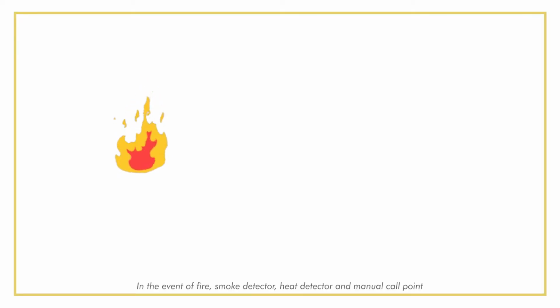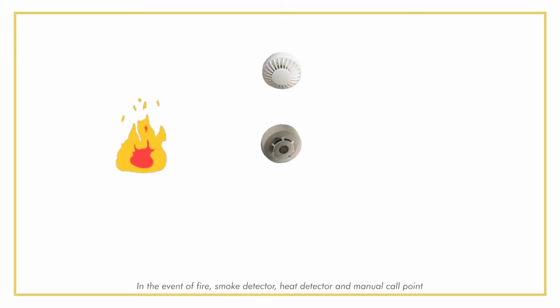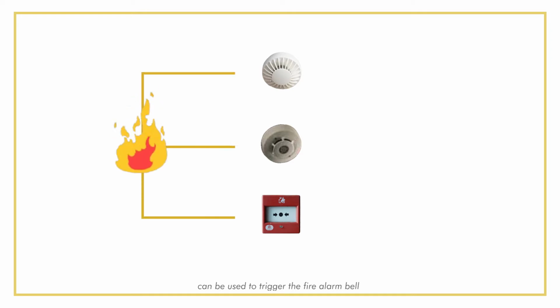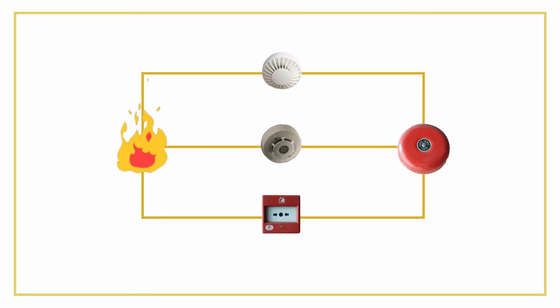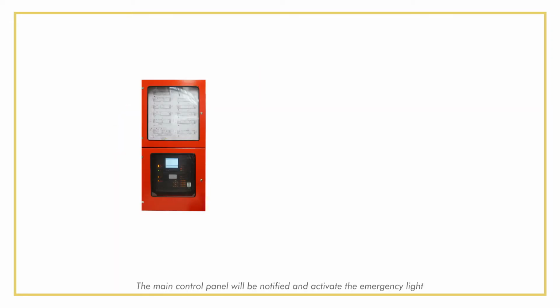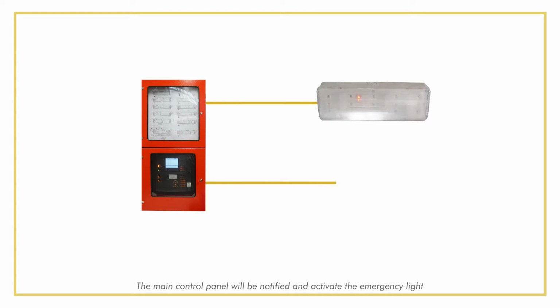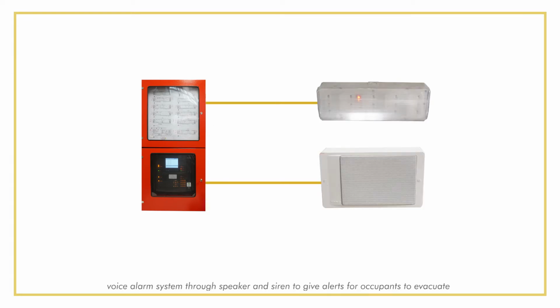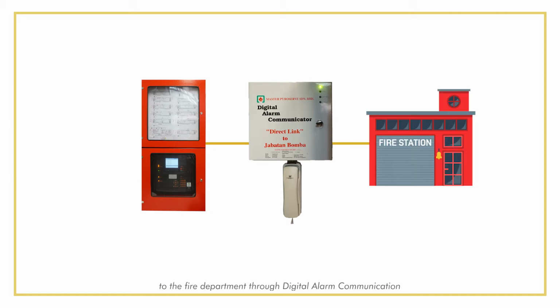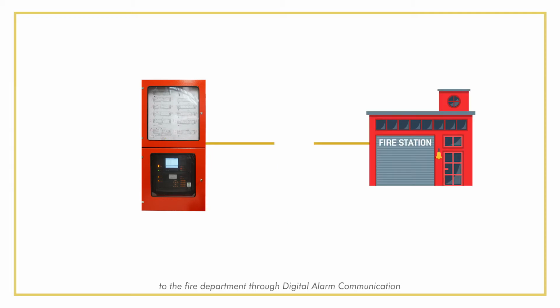In the event of fire, smoke detectors, heat detectors, and manual call points can be used to trigger the fire alarm bell. The main control panel will be notified and activate the emergency light, voice alarm system through speaker, and siren to give alerts for occupants to evacuate. At the same time, the control panel also transmits a signal to the fire department through digital alarm communication.